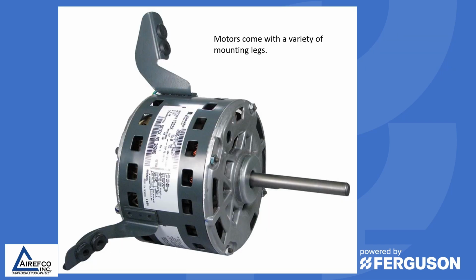Blower motors come in a variety of different sizes and shapes and mounting configurations. They come with a variety of mounting legs. You need to make sure that whatever type of mounting you have for the blower motor, you get it centered correctly so you eliminate the vibration and noise that can be contributed to insufficient mounting of these motors in blower housings.